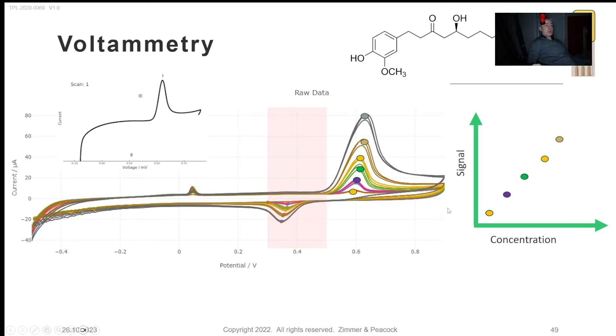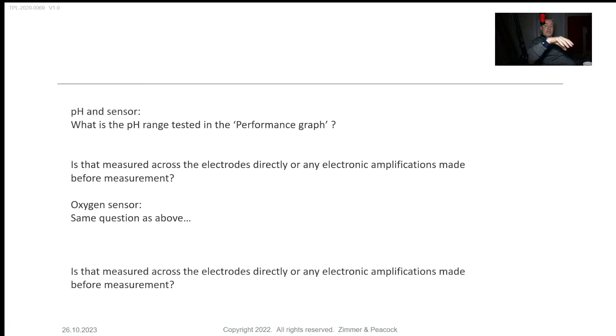This is pH and oxygen. Somebody's got hold of a couple of our data sheets, one on pH and one on oxygen, and they also want to know, are we doing any kind of amplification before measurement? The quick answer is we're not doing amplification before measurement. There is amplification happening in the electronics, but this is within the analog front end. There's not some pre-amplification and then some detection or reading of the signal.